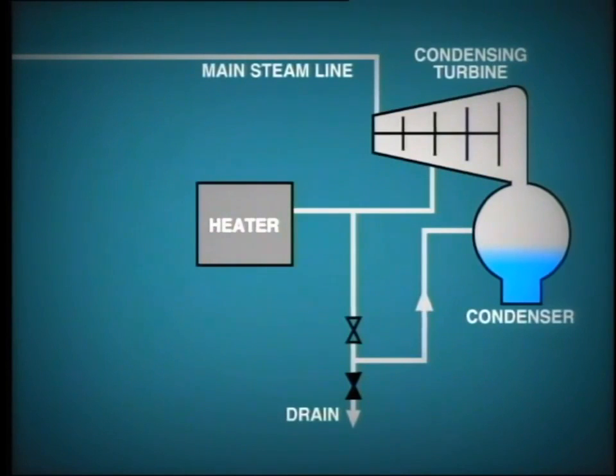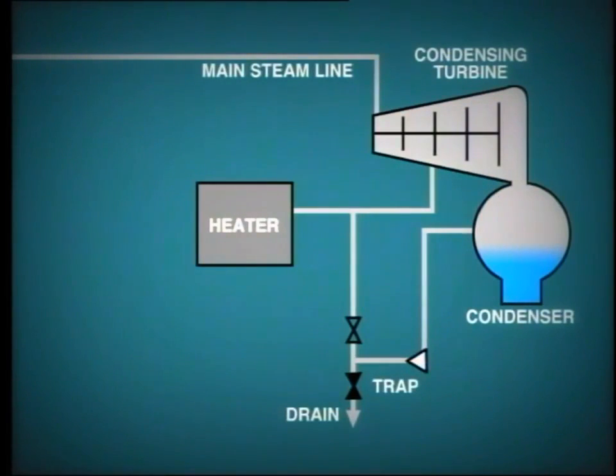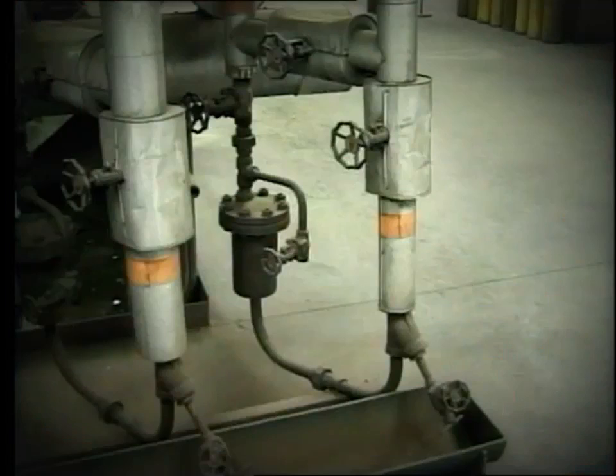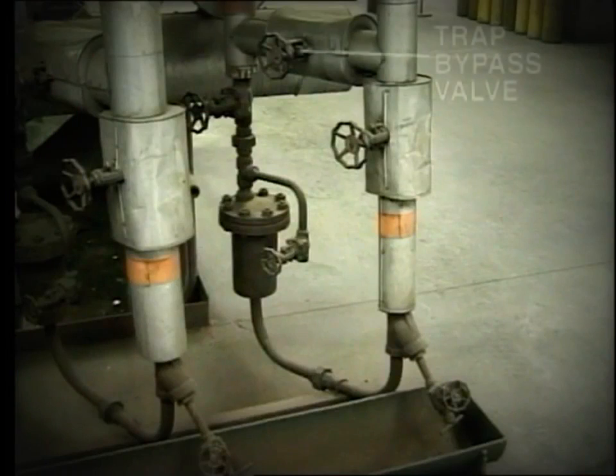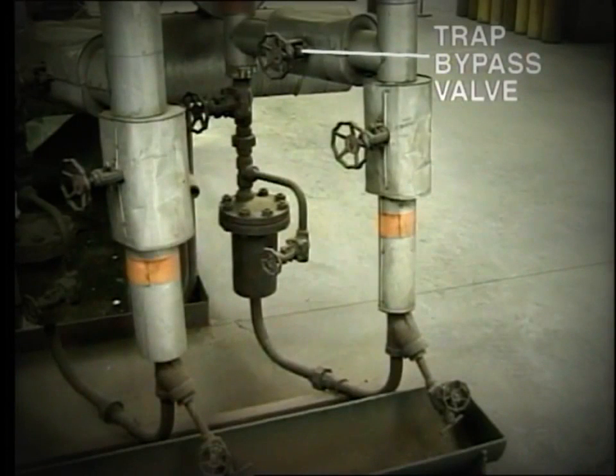Often these extraction line drains are fitted with steam traps which discharge automatically into the condenser. However, during start-up it is good practice to open the trap bypasses to make sure that all of the water is drained from the line.